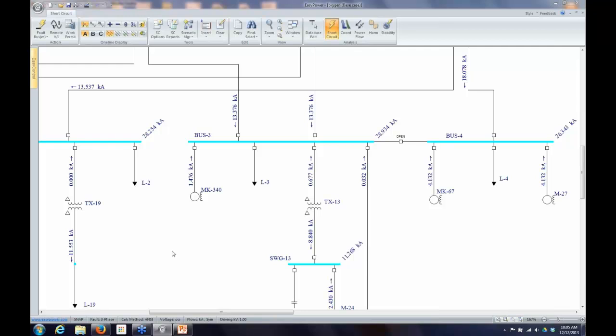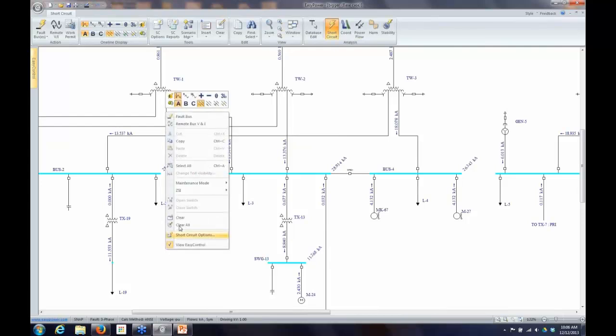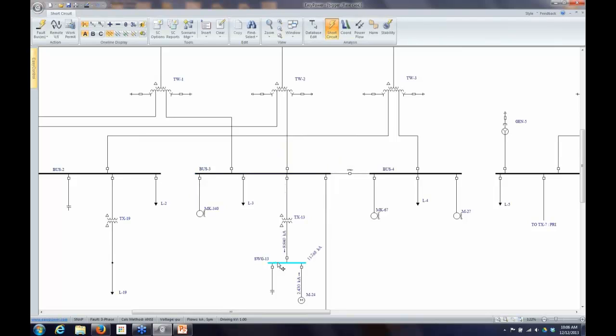If I have nothing selected and do Fault Buses, I fault every bus. I also have the option of only faulting selected buses. If I right-click I can clear my fault data. If I double-click on any one bus, it faults just that one bus — for example, double-clicking bus 3 will fault just that single bus. That's a quick way to look at fault current for any particular bus, useful for arc flash or equipment duty calculations.